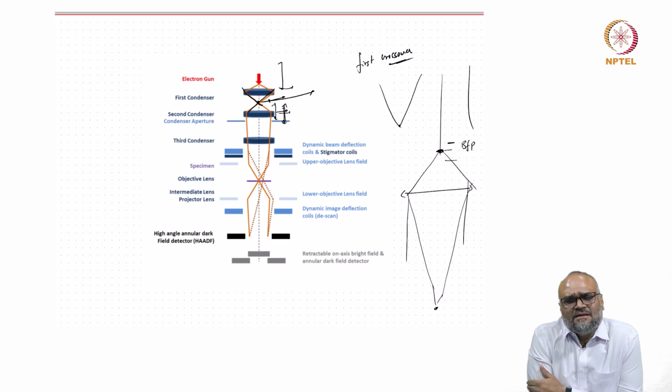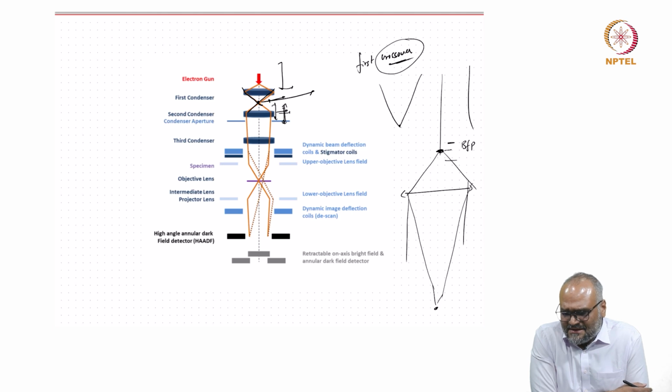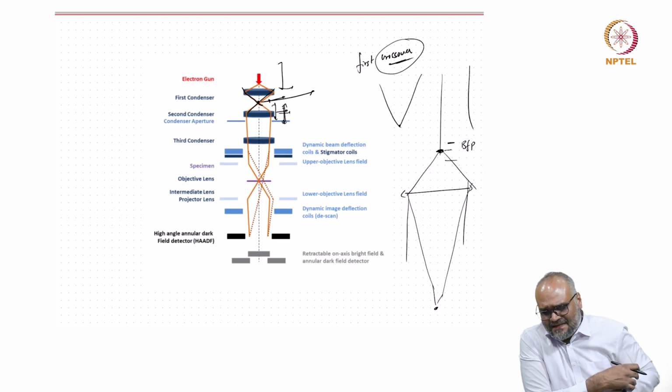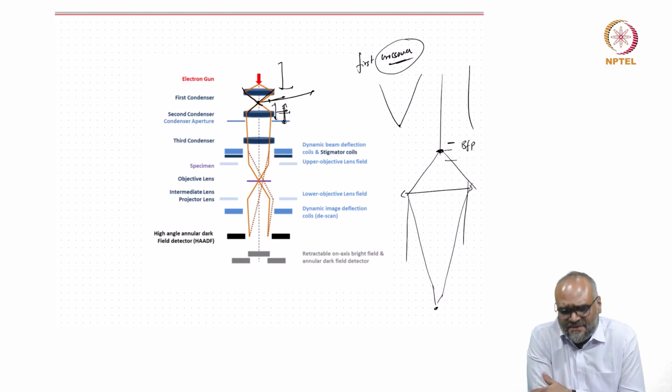is spread over. Now, why is this important, and how does a thermionic source matter? One of the important parameters is this crossover point for a thermionic emitter is not extremely fine. To have a better crossover and to have a very small probe, you would want to go to the field emitters. Let us now see how the thermionic emission functions.